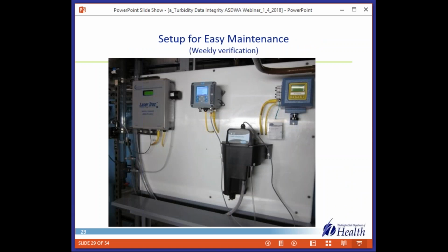The human component of data integrity at times may be the most important factor. It's hard to quantify that. One of the things we think is how you set up for maintenance and verification practices plays a huge role. This is a photo at the Everett Water Treatment Plant, and this is how it should be. The instruments are at eye and shoulder height, so easy access. You'll notice that they put a work shelf here to put your equipment down and do proper practices. You can do your verification, put your benchtop unit down here.